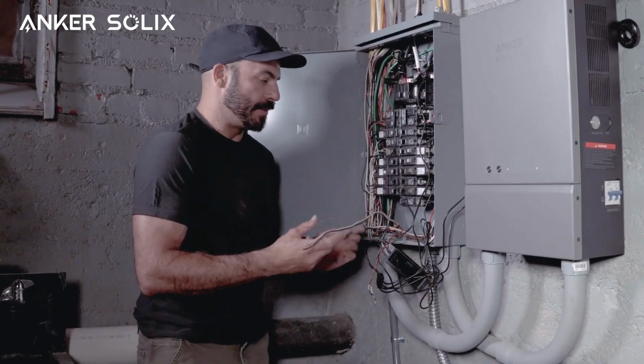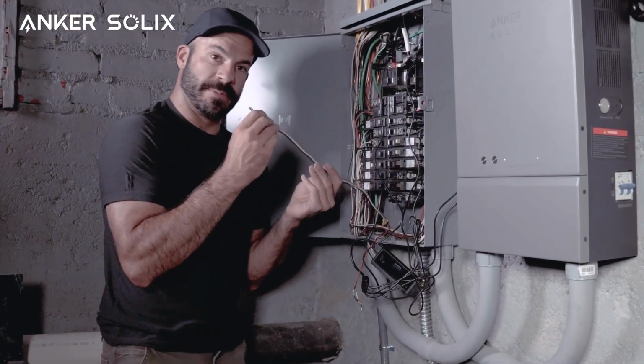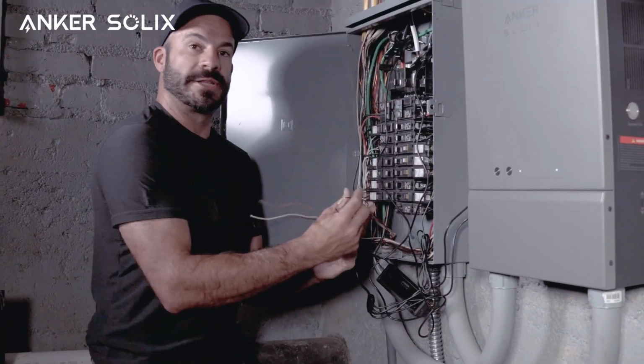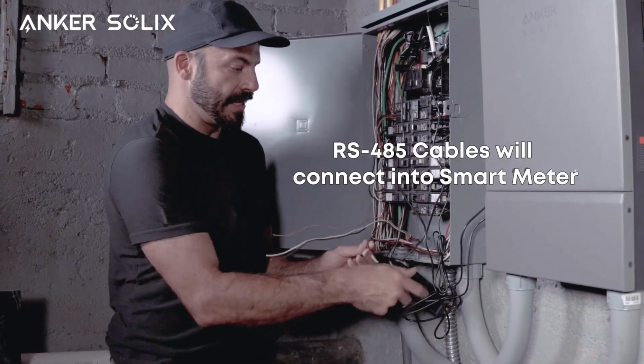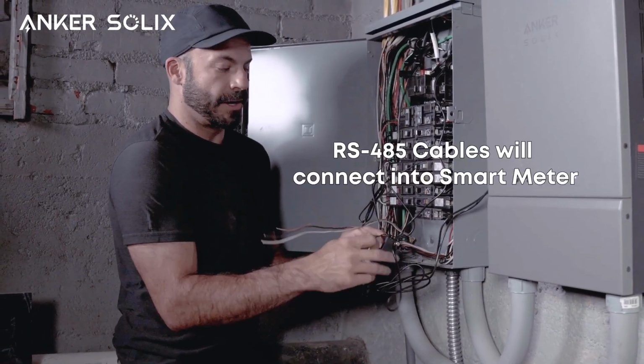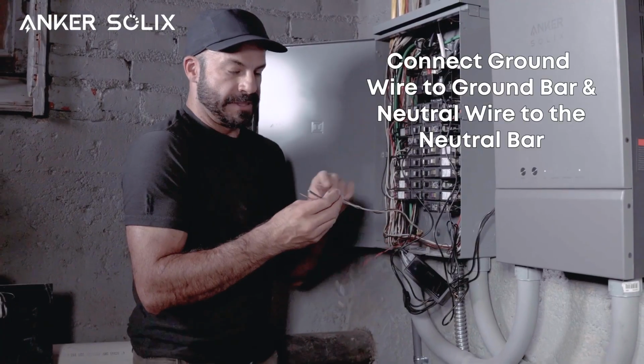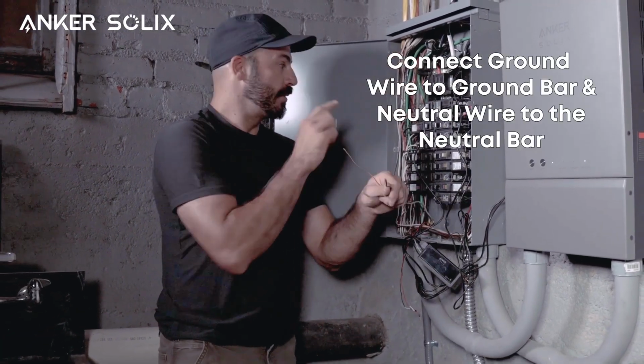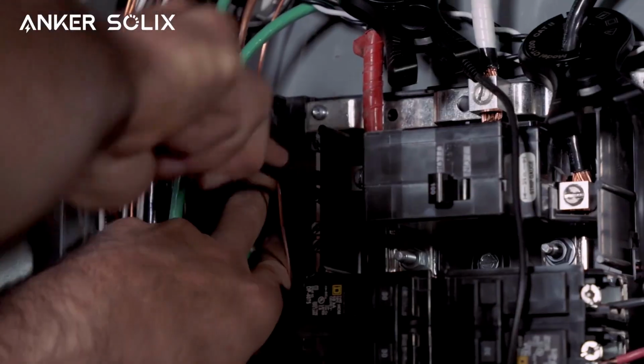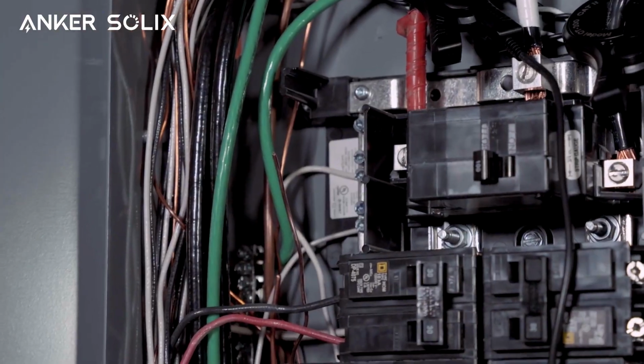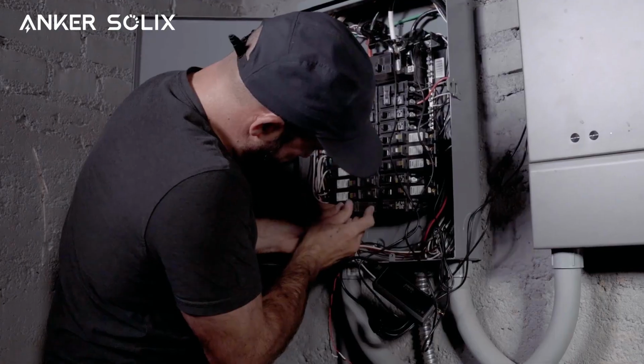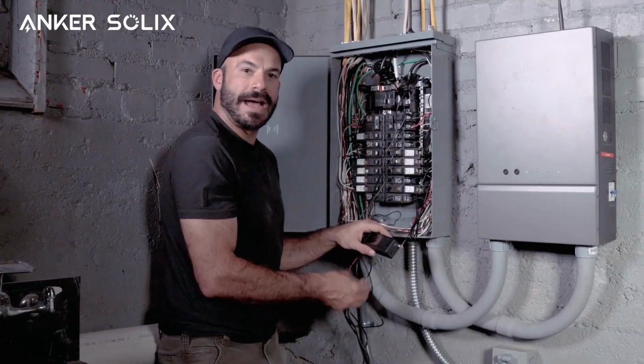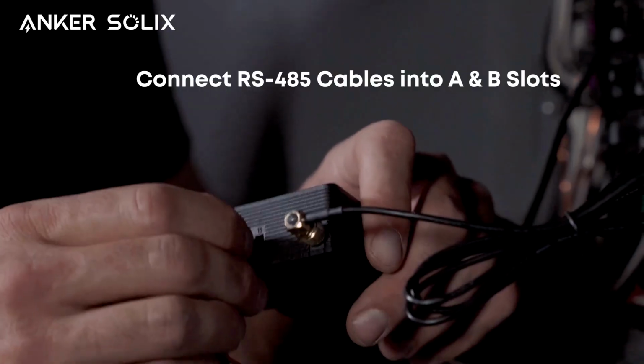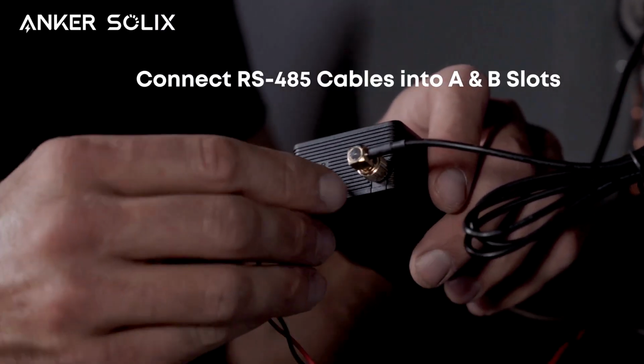Now we're back at the main breaker panel, and these are the wires coming in from our bidirectional inlet box along with the RS-485 cables. These are going to connect into our smart meter right here, and then we'll connect the ground to our ground bar, the neutral to our neutral bar, and then our line to our new 20 amp breaker. Now we're ready to make the last 2 connections into the smart home meter using the RS-485 cables in the A and B slots.